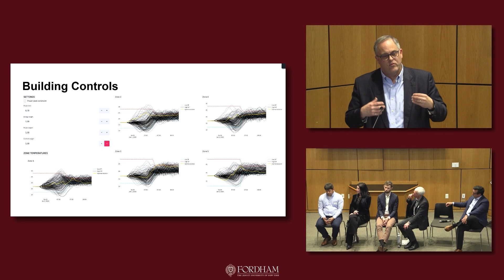What's really happening is you're flipping from reactive control, which is what the existing control sequence does—noticing the start of a trend it doesn't like and reacting to make a correction—to preemptive control, which knows there's going to be the start of an event in 2 hours and asks, how can I do something now to cancel out that event? The two work together.